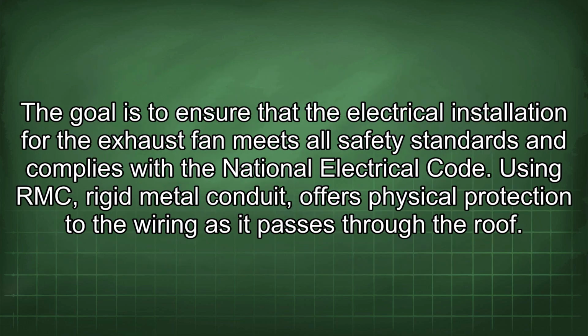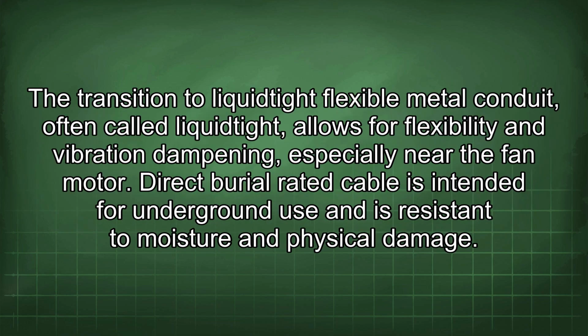The goal is to ensure that the electrical installation for the exhaust fan meets all safety standards and complies with the National Electrical Code. Using RMC, rigid metal conduit, offers physical protection to the wiring as it passes through the roof. The transition to liquidtight flexible metal conduit, often called liquidtight, allows for flexibility and vibration dampening, especially near the fan motor. Direct burial rated cable is intended for underground use and is resistant to moisture and physical damage.